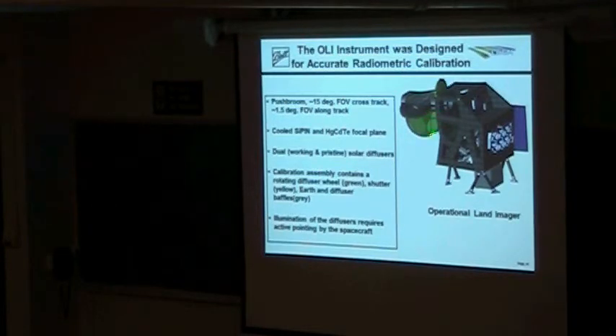The second diffuser in here is called the pristine diffuser, and it's used once every 6 months, because what these diffusers do over a period of time is degrade. The UV and the light will actually cause these things to degrade. If there is any contamination on these at all, then that UV light will cause the contamination to blacken, and so we get different reflectance properties off of this diffuser. So it's used as a backup for checking how much degradation we have in that system. In addition, we have calibration lamps mounted up here by our entrance aperture. These are tungsten lamps that have internal monitoring for radiometry and give a very stable illumination of the system all the way through to the focal plane. They're also used for calibration as well.